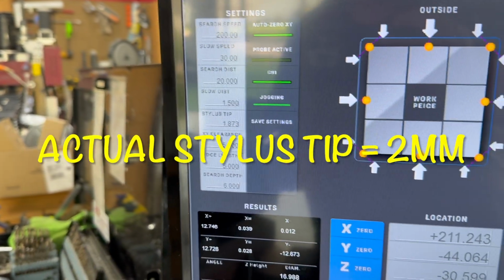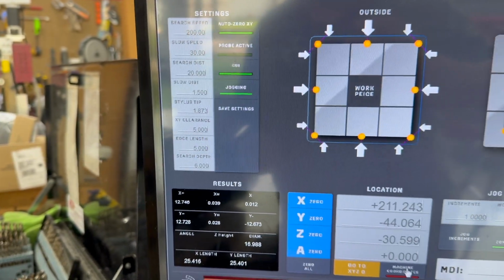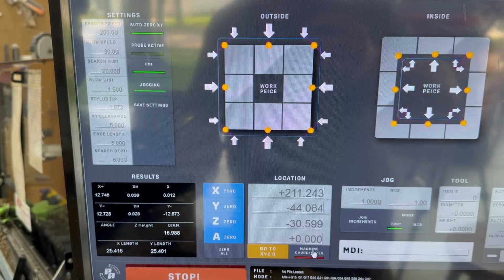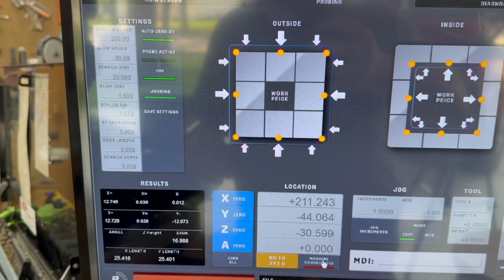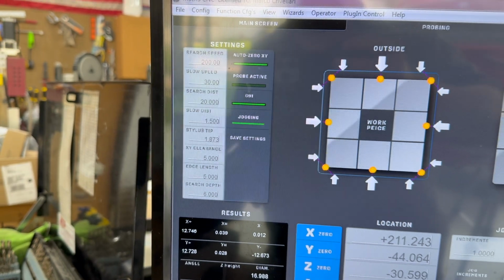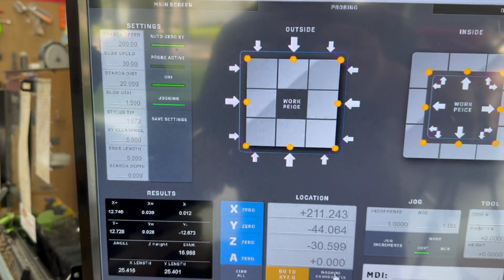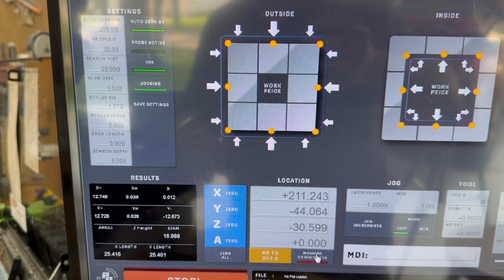Still not bad. But now that we've done this test, we can try to dial in the stylus tip as close as possible to actually take some measurements for repeatability. The diameter of the stylus did not matter much for this, but for measurement it does. So that's what we're going to do next.